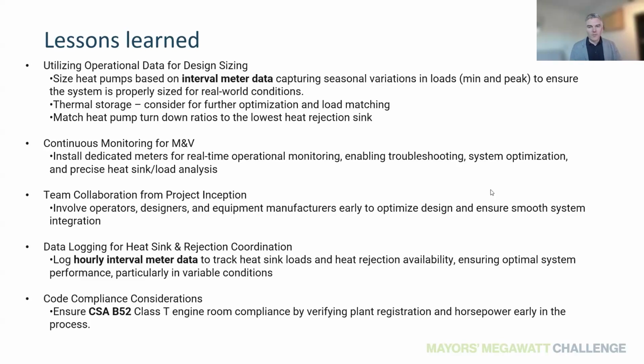Yeah, we've been involved in doing heat recovery from ammonia systems basically since the inception. We've done quite a lot of this, particularly when it comes to lower grade heat integration around 95. Offering an ammonia heat pump into the Canadian refrigeration market, specifically for arenas, was a bit of a newer implementation that was relatively easy to prefabricate in an offsite facility and just put in. Some of the difficulties we encountered with an existing facility were simply fitting the equipment through the door. For this one, we had to split the package into two independently designed systems and then fit them together on site, which definitely had some execution challenges associated with it.